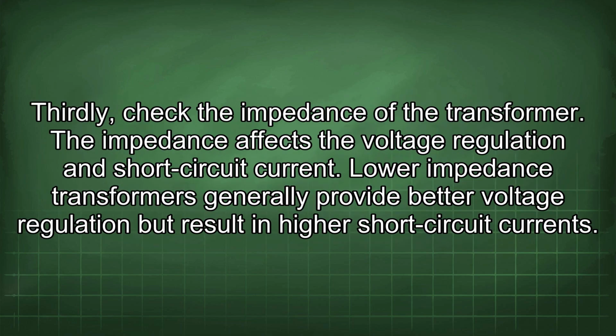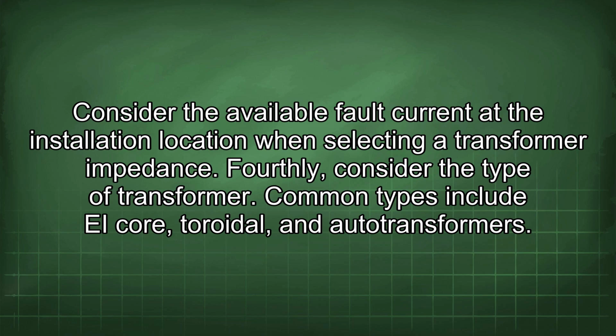Thirdly, check the impedance of the transformer. The impedance affects the voltage regulation and short-circuit current. Lower impedance transformers generally provide better voltage regulation, but result in higher short-circuit currents. Consider the available fault current at the installation location when selecting a transformer impedance.